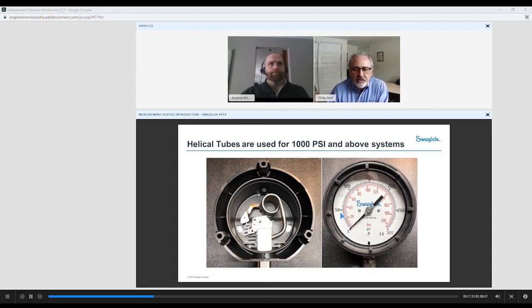Once again, just noting that the markings on the face of the gauge are laid out, so regardless of the manufacturer, if they're manufacturing to ASME B40.100, those markings will be indicated in exactly the same way. This gauge as well, it has the lens ring that we talked about earlier in the presentation. This can be removed. The lens can be taken out, and this is a calibratable gauge. So this gauge can be calibrated. Most gauges tend to be calibrated on an annual basis. We have some customers that calibrate every 3 months, and we have others that leave them up to 3 years. So that is dictated by either your ISO or your QA. So these are calibratable and adjustable movements.